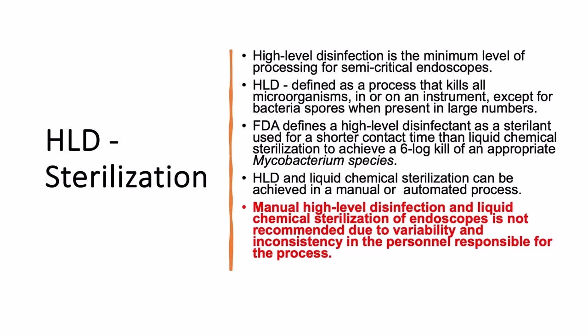High-level disinfection, as you know, is a process that kills all microorganisms in or on an instrument, except for large numbers of bacterial spores. A disinfectant is defined by the FDA as a sterilant used for a shorter contact time than liquid chemical sterilization to achieve a 6-log kill of an appropriate mycobacterium species. High-level disinfection and liquid chemical sterilization can be achieved manually or mechanically.